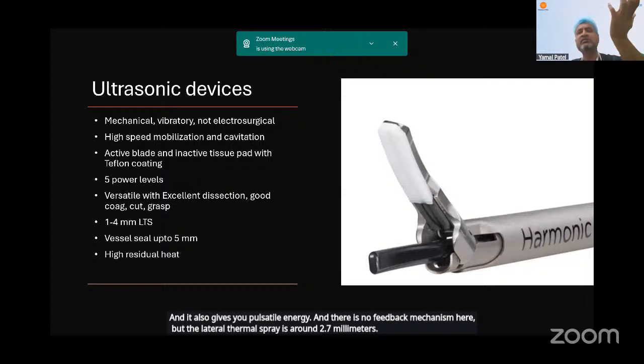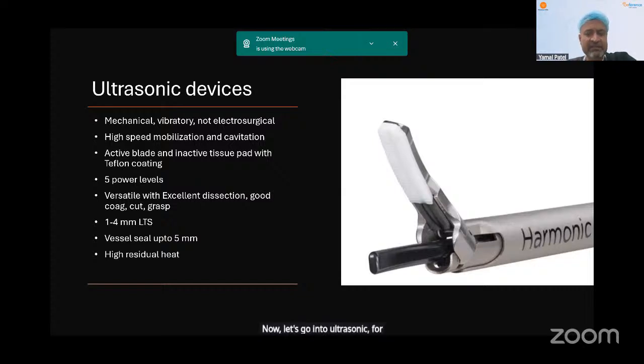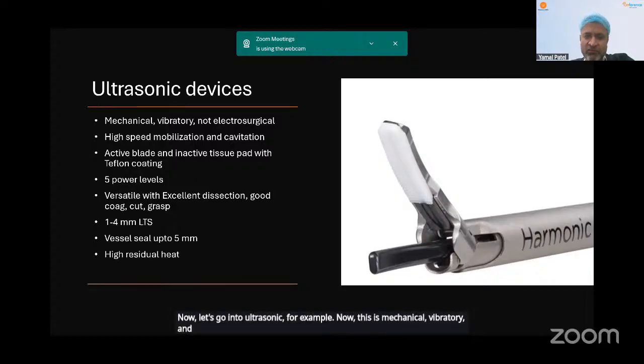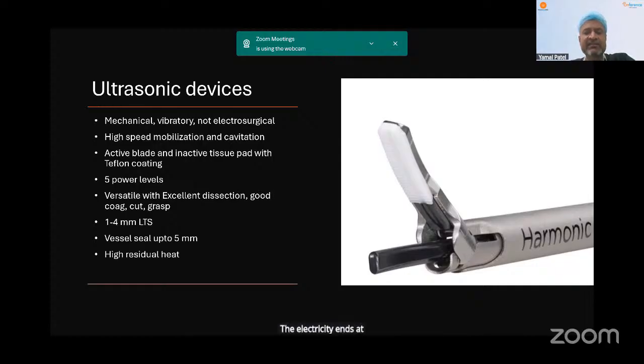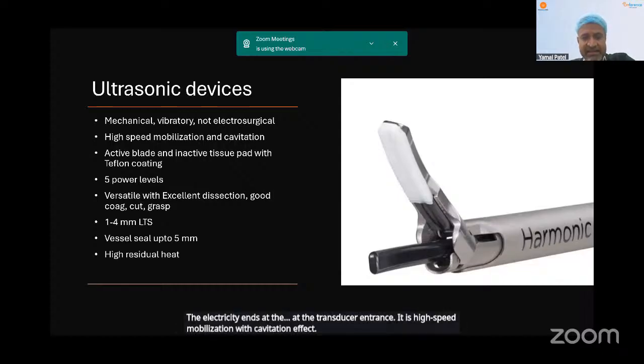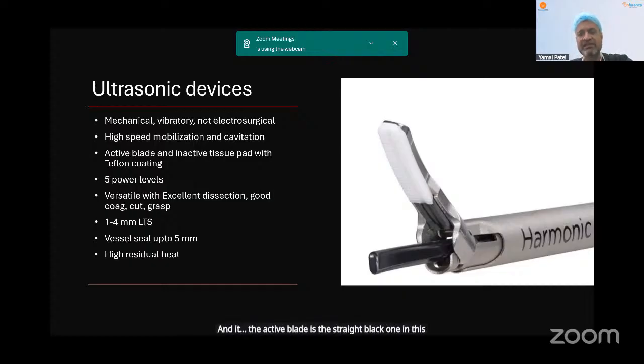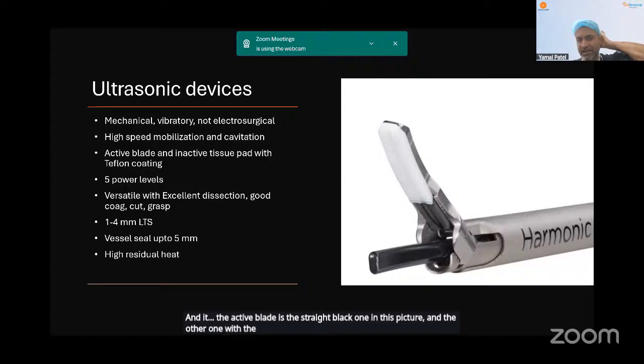Now let's go into ultrasonic, for example. Now this is mechanical, vibratory, and not electrosurgery. There is no electrosurgery here. It is mechanical energy. The electricity ends at the transducer entrance. It is high-speed mobilization with cavitation effect. And the active blade is the straight black one in this picture. And the other one with the Teflon tissue pad is actually the inactive blade with 5 power levels.